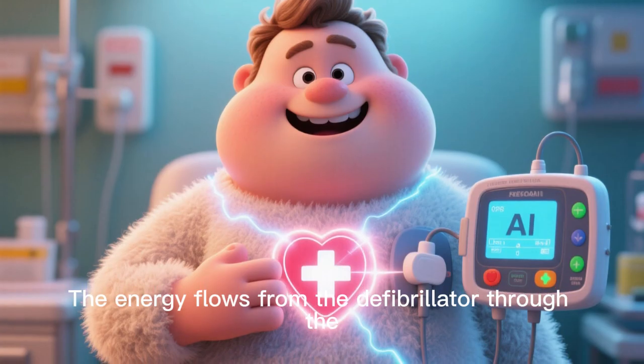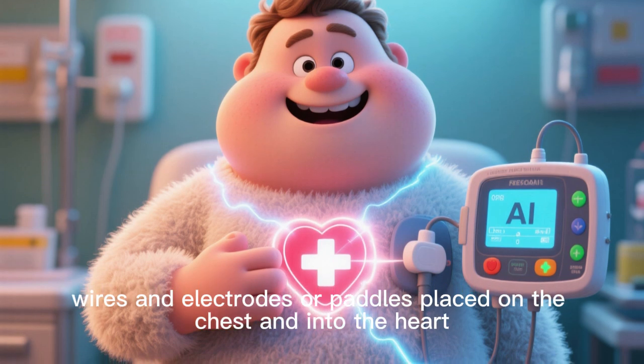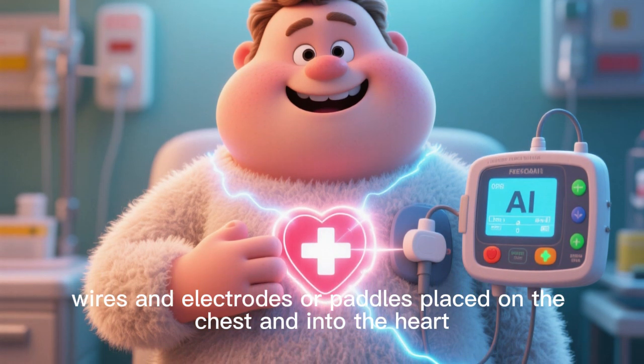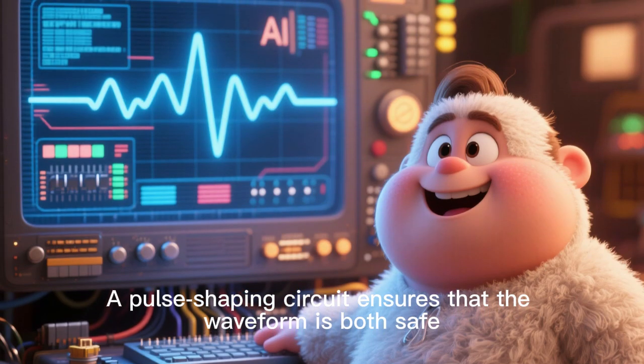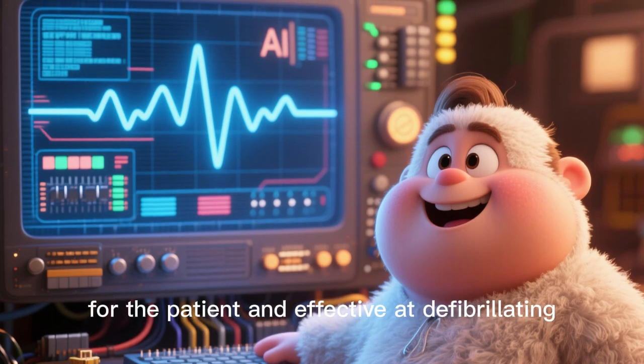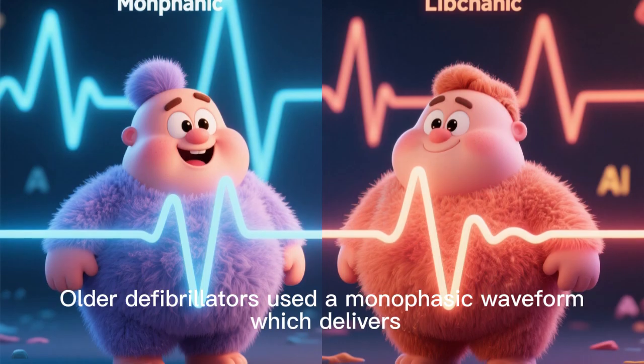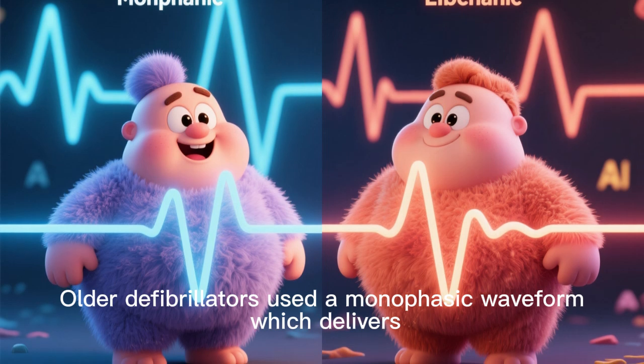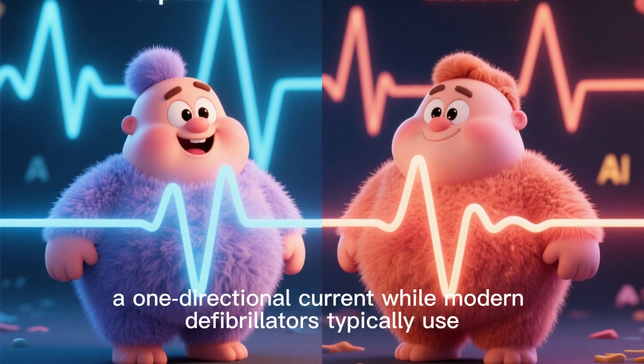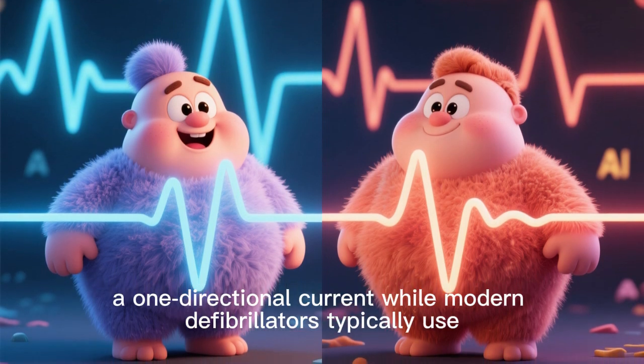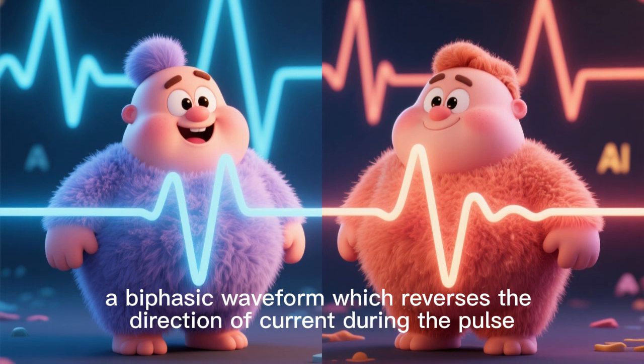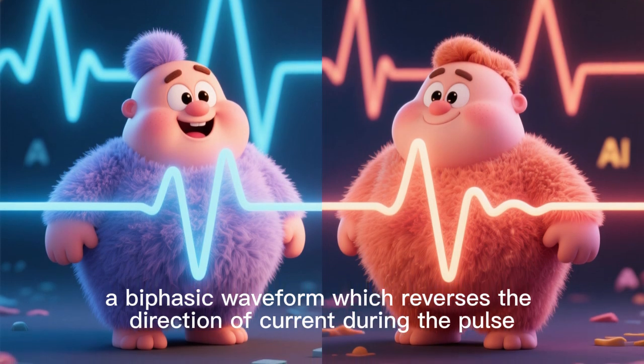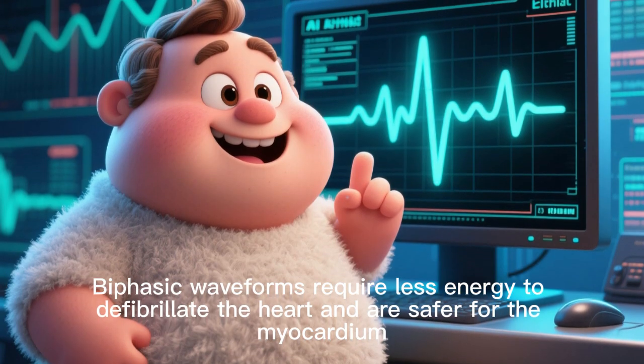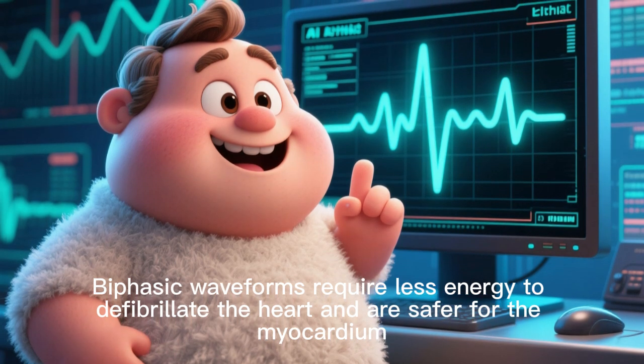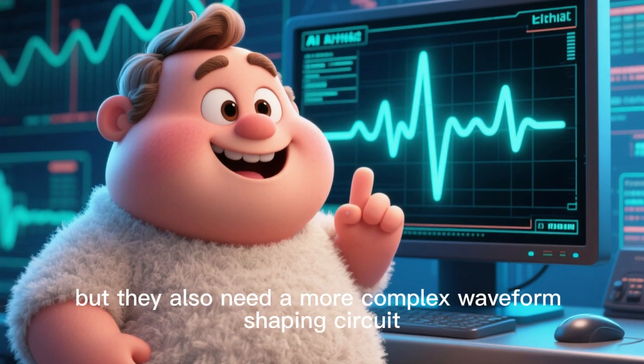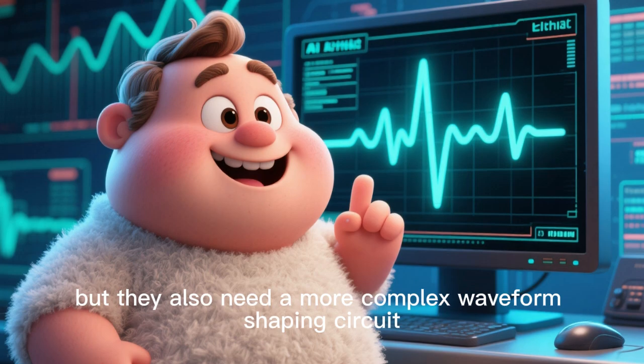The energy flows from the defibrillator through the wires and electrodes or paddles placed on the chest and into the heart. A pulse-shaping circuit ensures that the waveform is both safe for the patient and effective at defibrillating. Older defibrillators used a monophasic waveform, which delivers a one-directional current, while modern defibrillators typically use a biphasic waveform, which reverses the direction of current during the pulse. Biphasic waveforms require less energy to defibrillate the heart and are safer for the myocardium. But they also need a more complex waveform shaping circuit.